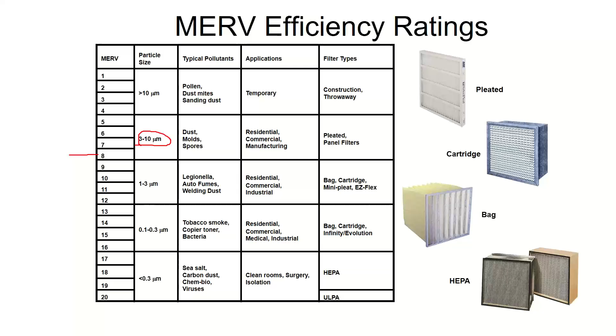If it fits through the hole in the first filter, it's going to fit through the hole in the second filter, right? So no, it's not additive. A MERV 8 plus another MERV 8 equals MERV 8. You don't get any extra, you don't even get to MERV 9. It's the exact same thing. The only thing it does is keep the second filter pretty clean. You don't get anything extra.